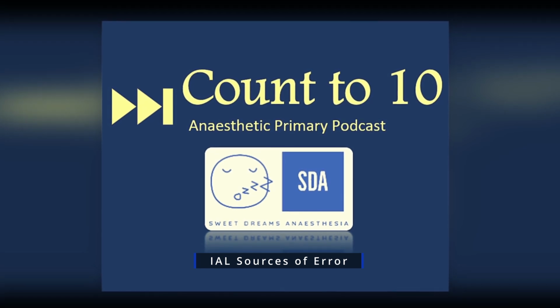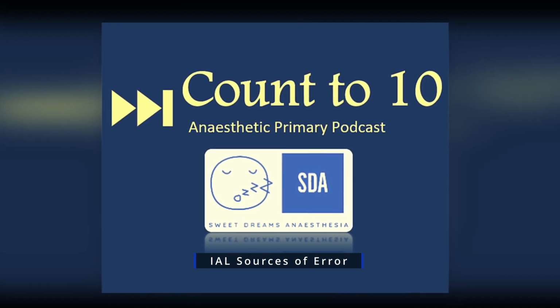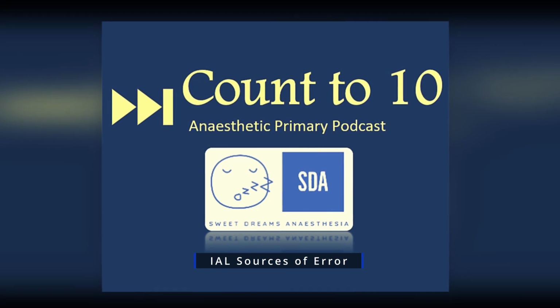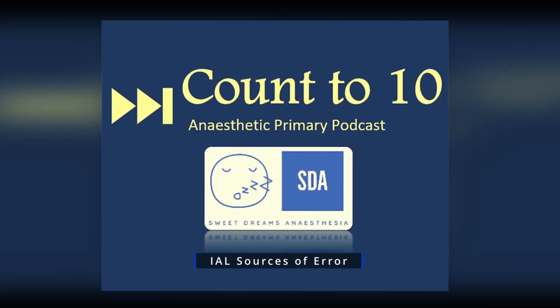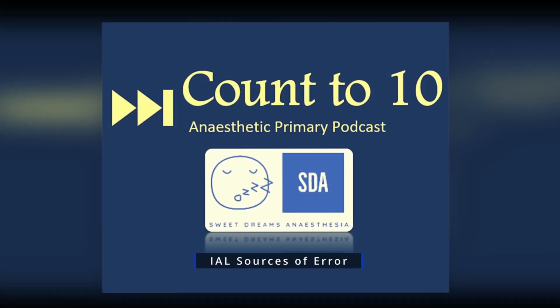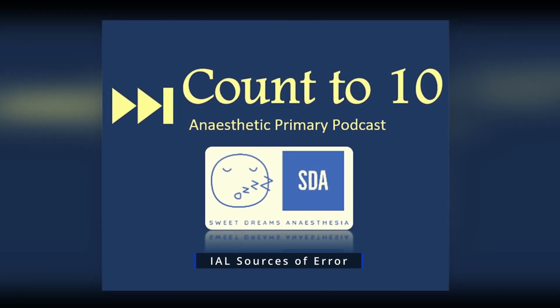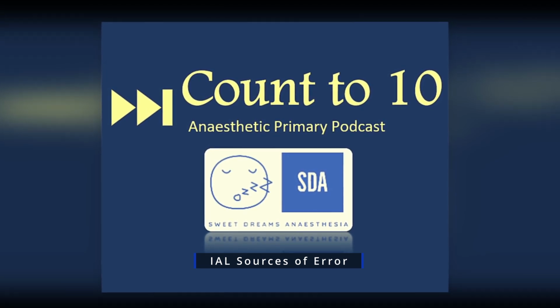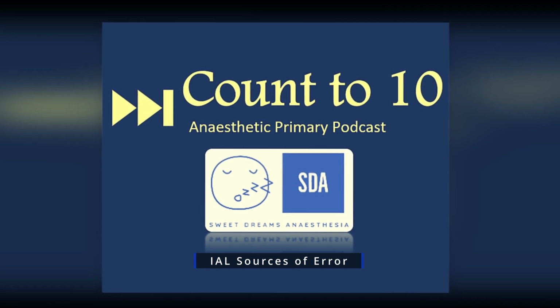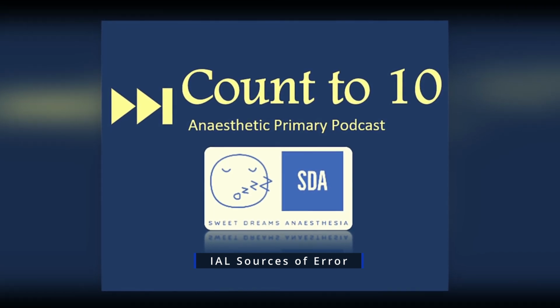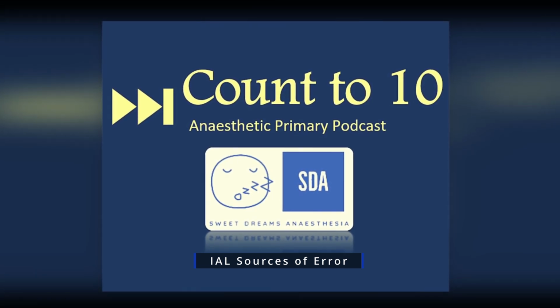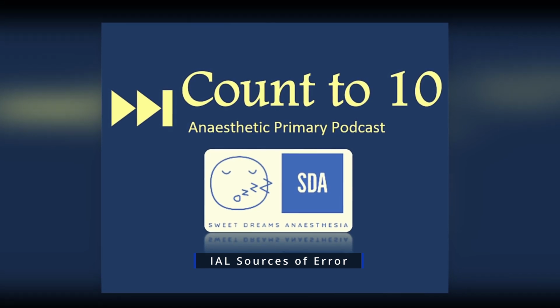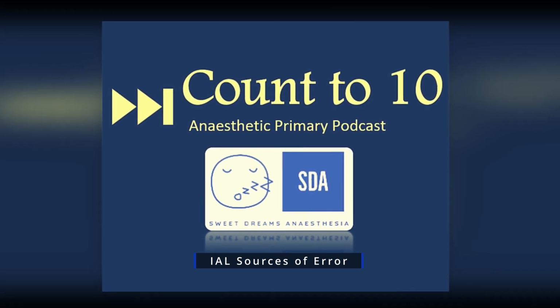With an arterial line, you want the natural frequency of the arterial line system to be well above the natural frequency of arterial pulsations. The maximum natural frequency of arterial pulsations we commonly say is going to be 3 Hz. That's because the natural frequency of arterial pulsations is based on heart rate. Typically, heart rates are between 60 to 100 beats per minute. This is roughly 1 to 1.5 Hz.